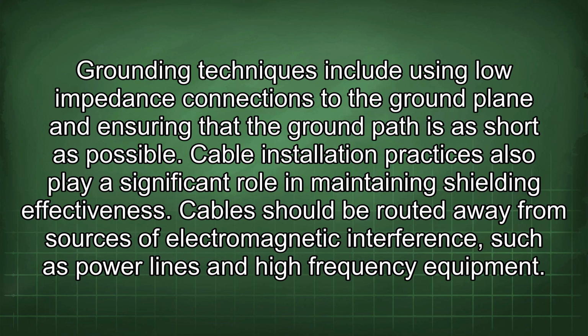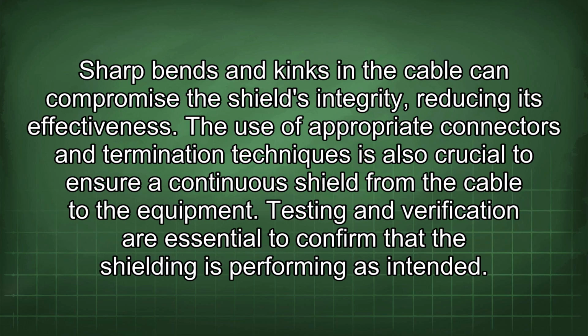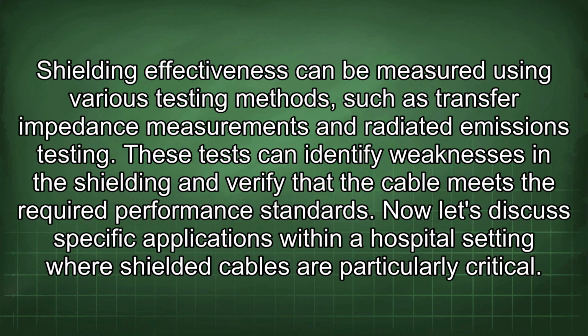Cables should be routed away from sources of electromagnetic interference such as power lines and high-frequency equipment. Sharp bends and kinks in the cable can compromise the shield's integrity, reducing its effectiveness. The use of appropriate connectors and termination techniques is also crucial to ensure a continuous shield from the cable to the equipment. Testing and verification are essential to confirm that the shielding is performing as intended. Shielding effectiveness can be measured using various testing methods, such as transfer impedance measurements and radiated emissions testing. These tests can identify weaknesses in the shielding and verify that the cable meets the required performance standards.